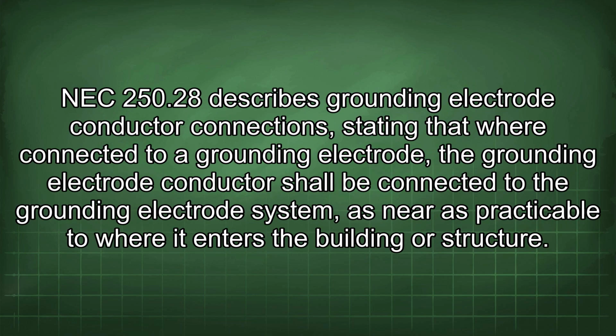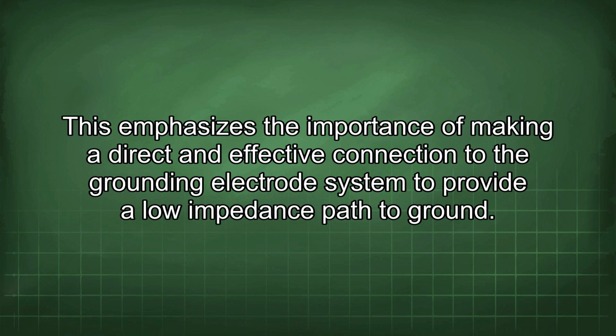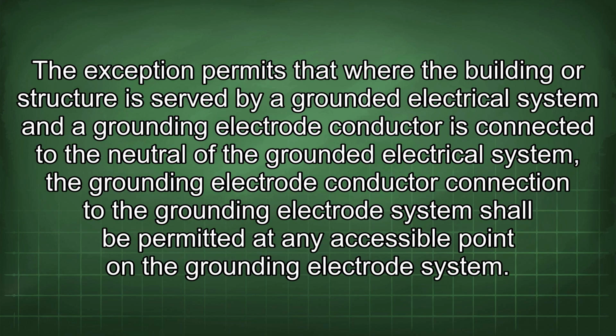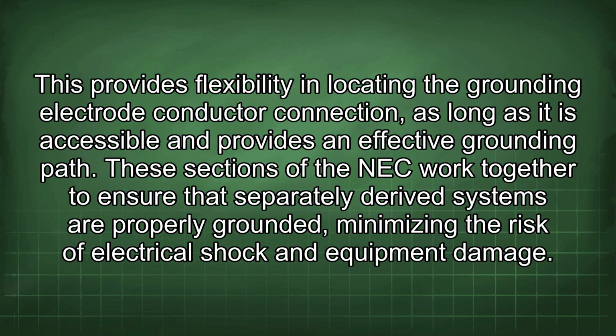NEC 250.28 describes grounding electrode conductor connections, stating that where connected to a grounding electrode, the grounding electrode conductor shall be connected to the grounding electrode system as near as practicable to where it enters the building or structure. This emphasizes the importance of making a direct and effective connection to the grounding electrode system to provide a low impedance path to ground. The exception permits that where the building or structure is served by a grounded electrical system and the grounding electrode conductor is connected to the neutral of the grounded electrical system, the grounding electrode conductor connection to the grounding electrode system shall be permitted at any accessible point in the grounding electrode system. This provides flexibility in locating the grounding electrode conductor connection, as long as it is accessible and provides an effective grounding path.